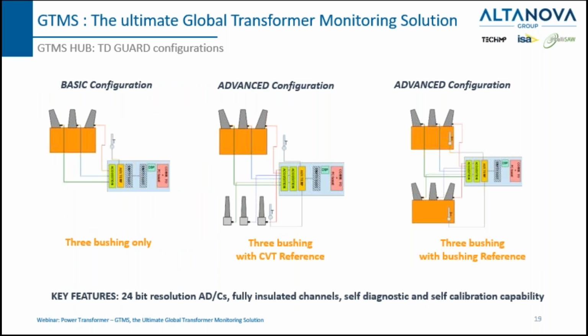Here an example of the basic configuration, starting from the left. You can see here 3 bushings only or 6 bushings connected to the capacity tap using a dedicated sensor up to the EDS unit. And in these other 2 cases, the advanced configuration, when we have 3 bushings plus CVT as reference, or on the right, again the advanced configuration with 3 bushings with another 3 bushings that we use as reference.